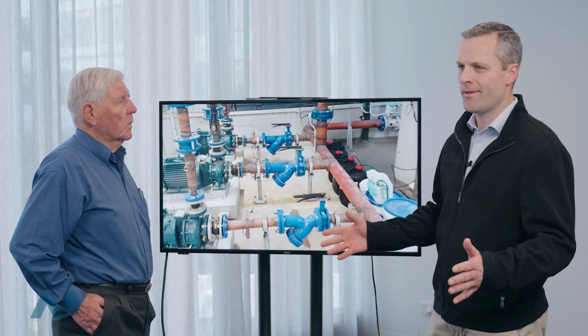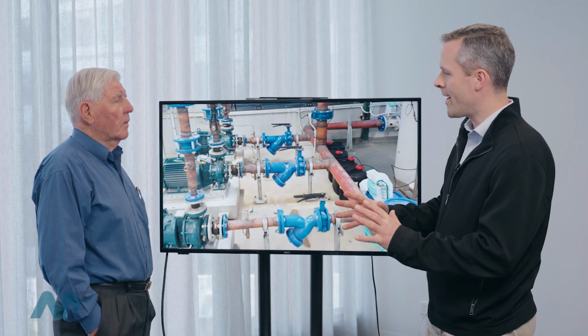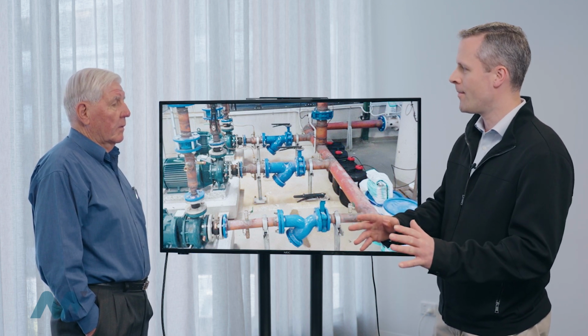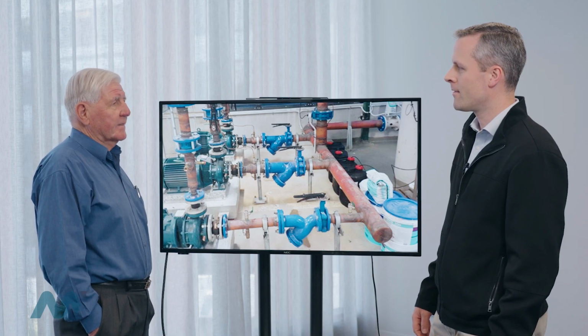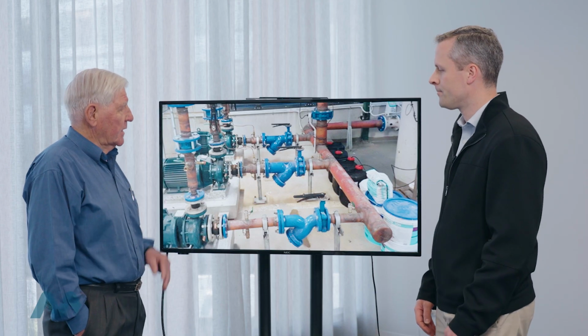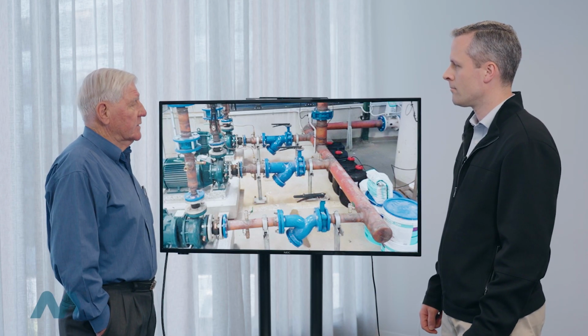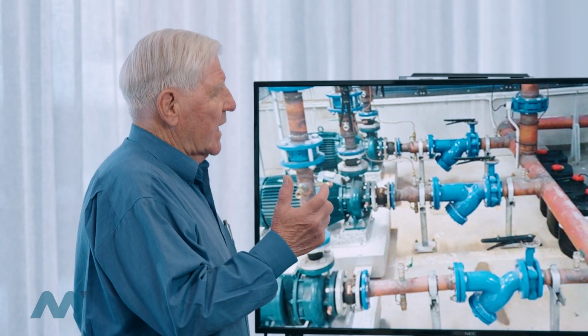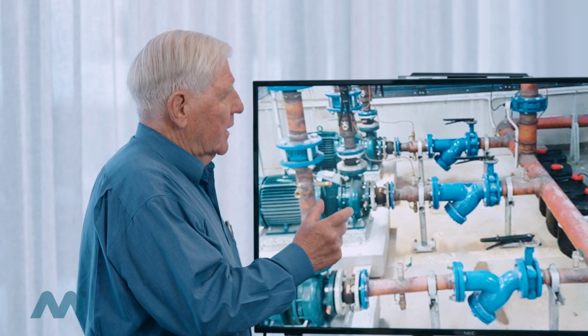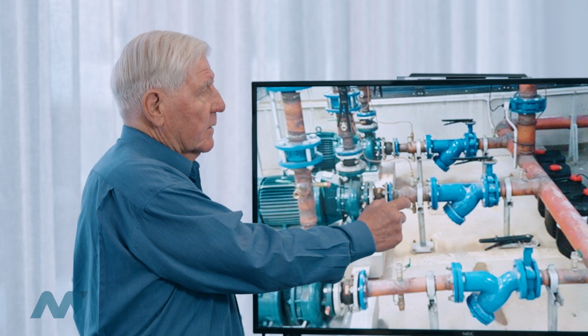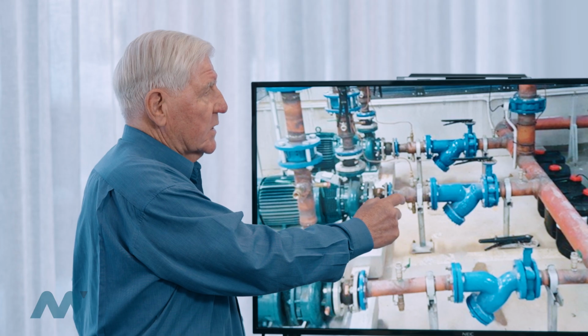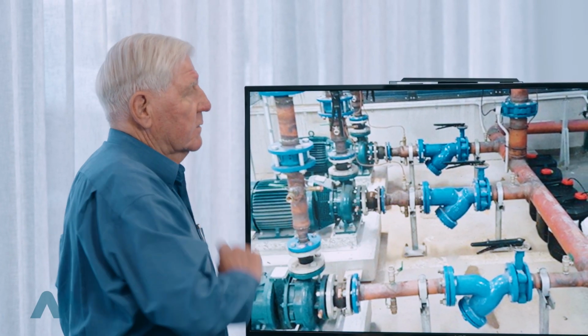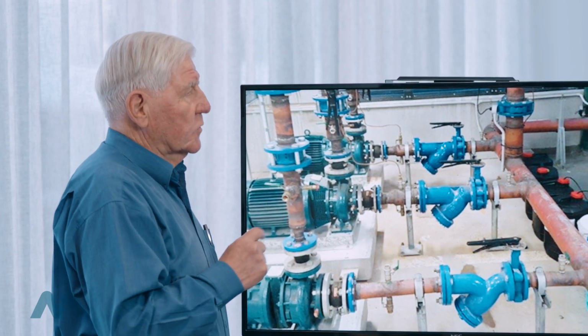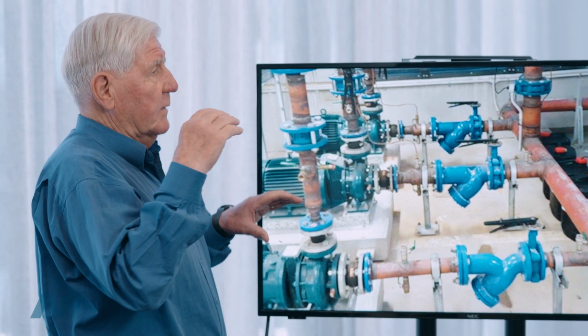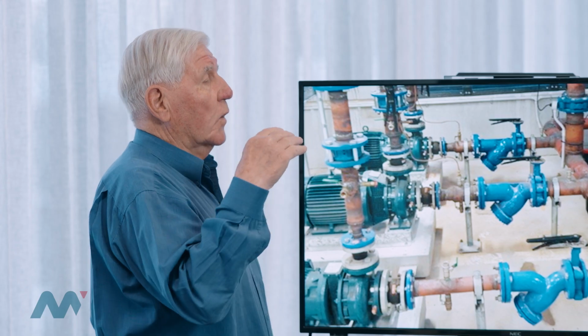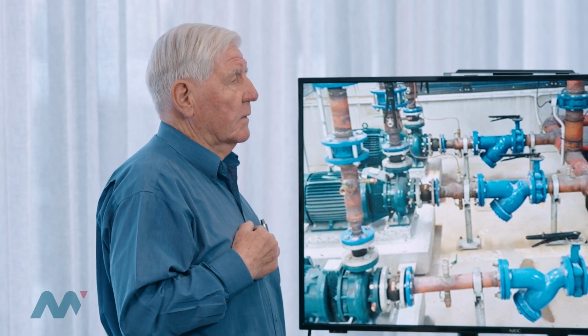So let me ask you then, why do they make a pump with an 80 mil suction and at 2,900 RPM, the velocity's much, much higher? Because the pumps are built to a standard, either an ISO or a DIN standard for an end suction pump, and then there are nominated flow rates and nominated flange sizes. But what we're normally expecting is that the pipe alteration in diameter takes place very close to the pump suction flange, and that it's an eccentric reducer. So you've got a relatively smooth path coming into the eccentric reducer and going into the eye of the impeller. Because you've got to remember that in this particular pump design, we've got liquid coming in this direction and an impeller rotating in that direction, and you want as straight a flow as you possibly can going into the eye of the impeller for good hydraulic results.